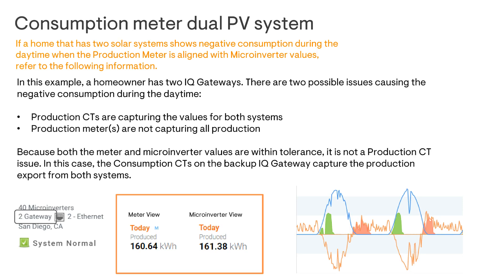In this case, the consumption CTs on the secondary IQ gateway capture the production export from both systems. If both systems are exporting excess production to the grid through the consumption CTs, you have two options to troubleshoot.